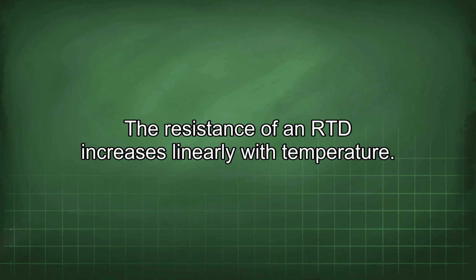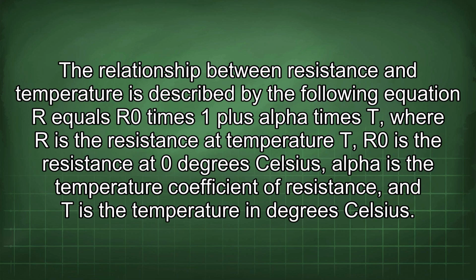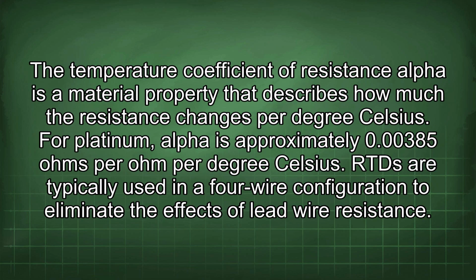The resistance of an RTD increases linearly with temperature. The relationship between resistance and temperature is described by the following equation: R equals R0 times (1 plus alpha times T), where R is the resistance at temperature T, R0 is the resistance at 0 degrees Celsius, alpha is the temperature coefficient of resistance, and T is the temperature in degrees Celsius. The temperature coefficient of resistance alpha is a material property that describes how much the resistance changes per degree Celsius. For platinum, alpha is approximately 0.00385 ohms per ohm per degree Celsius.